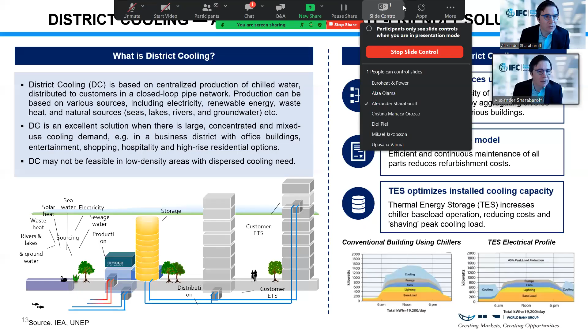District cooling, the concept itself, is fairly straightforward. It's a concept based on economies of scale, and instead of every building or end user having its own cooling infrastructure - cooling equipment, chillers, split AC units, VRF and so on - district cooling assumes centralized production of chilled water by a central cooling plant or plants, which are then connected to end users or buildings, typically by an underground network of pre-insulated polyurethane pipelines, connected to the buildings themselves through an energy transfer station. And of course, the energy transfer station is nothing else than a good old heat exchanger.